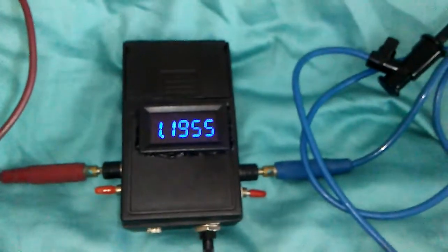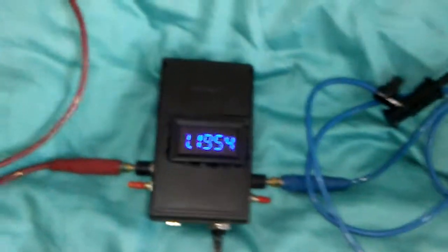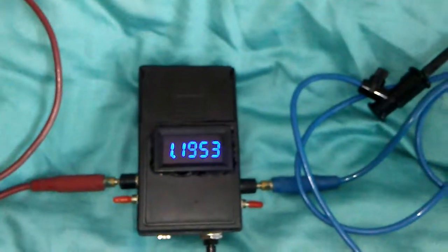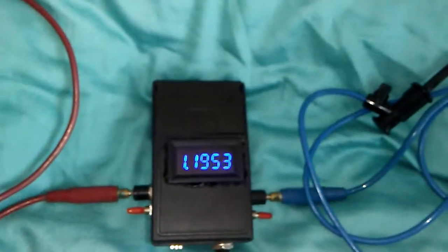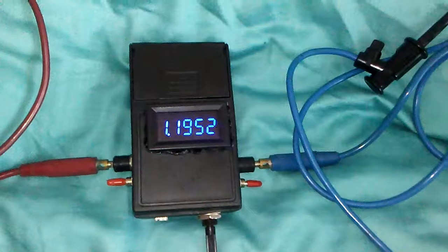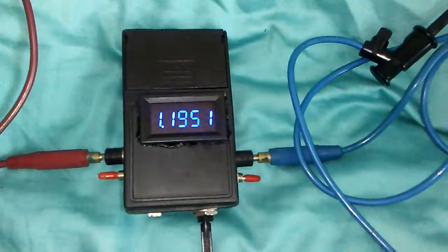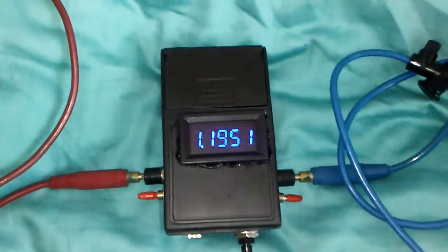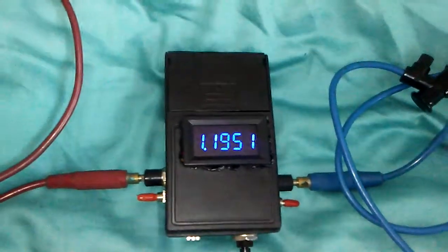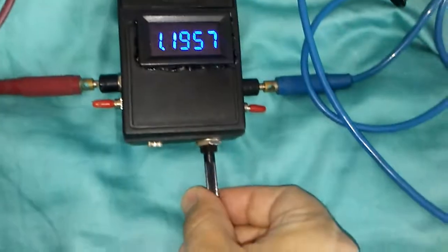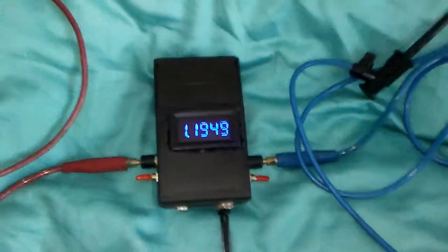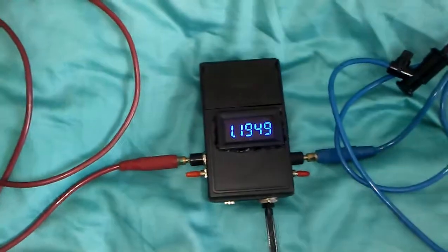When I'm pressing the calibration key it is going to 1.20 ohm high-quality resistor. If the number goes below or more than 1.195, it needs to be calibrated with this volume. This is the calibrated point and I'm going to start the test.